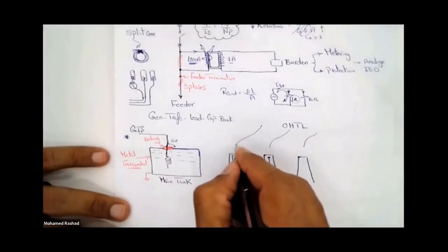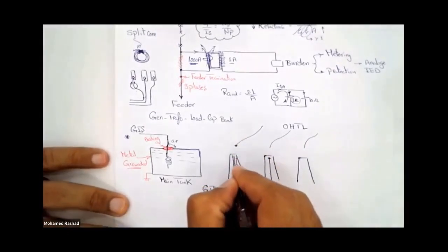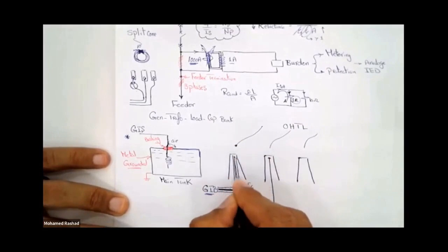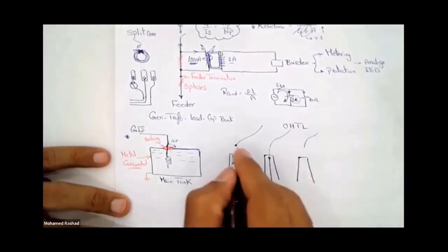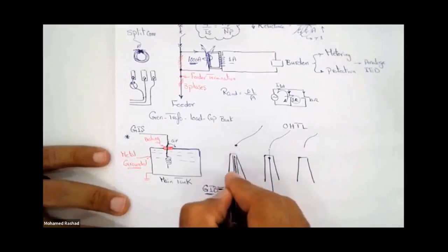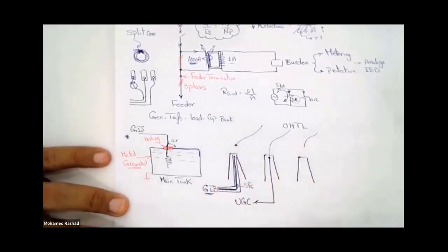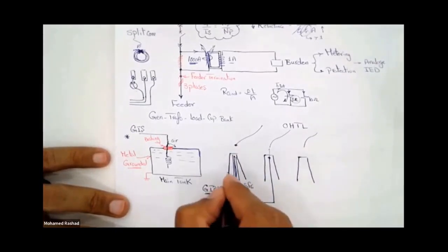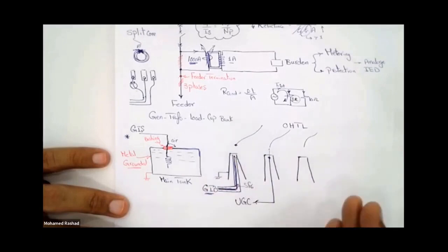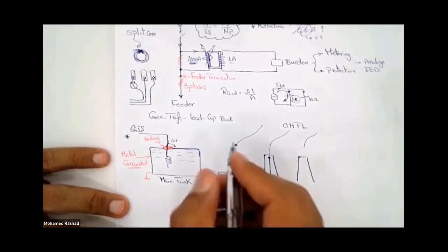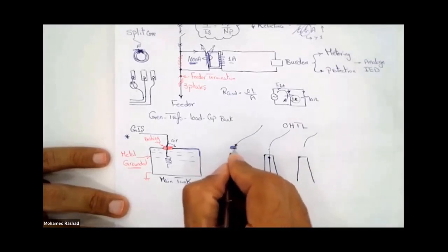In both cases, you want to connect this to the internal conductor present here, or convert it to connect to the cable. In both cases, you cannot connect it directly like this. The gantry structure is also metallic, and this metallic structure is grounded. That's why you always see the bushing here, which you connect above.